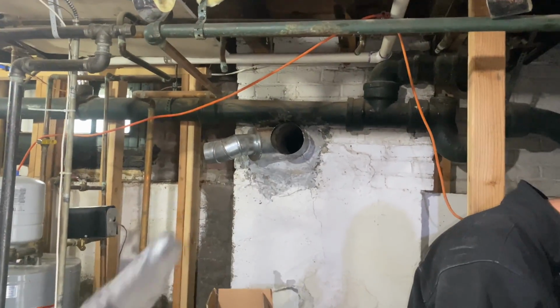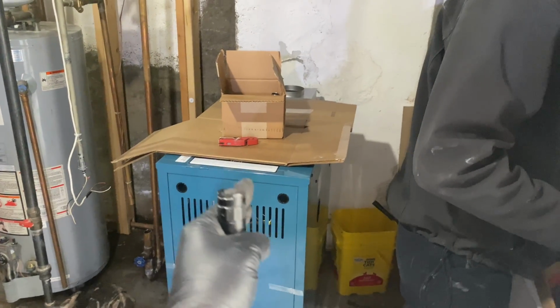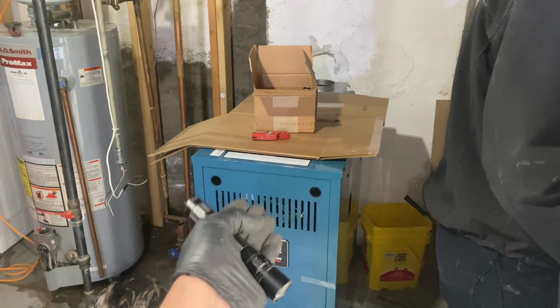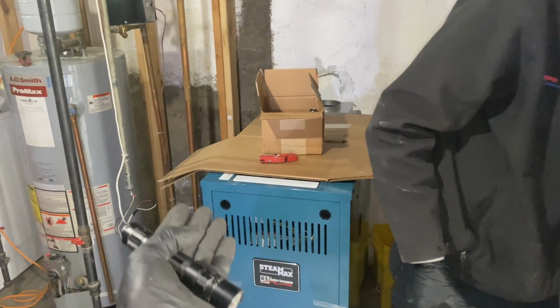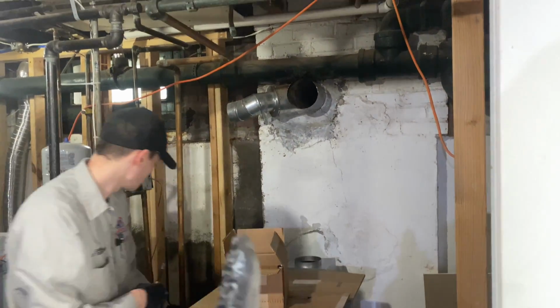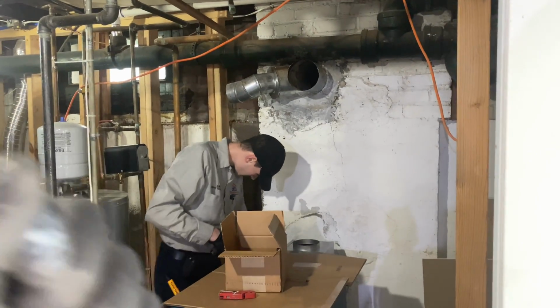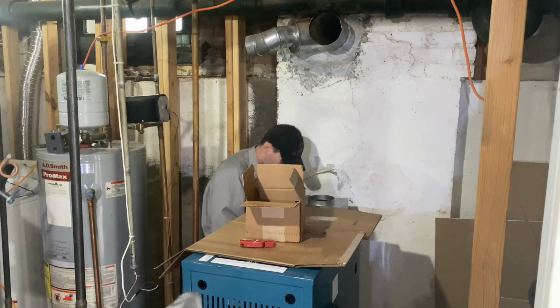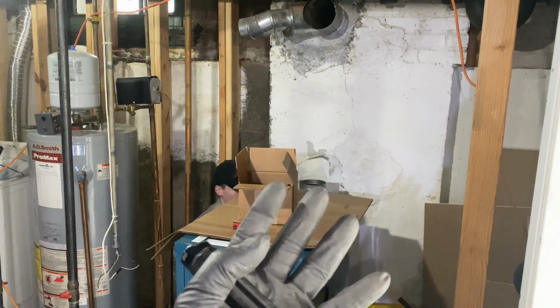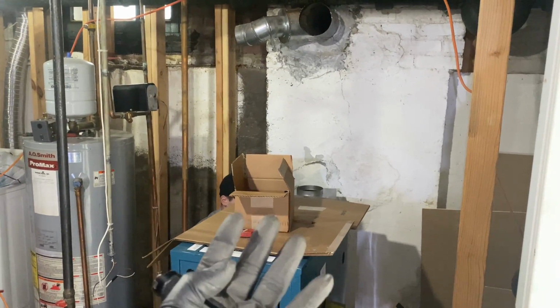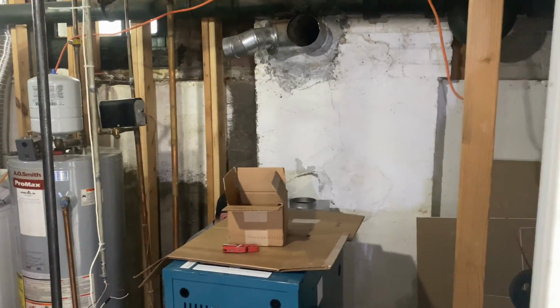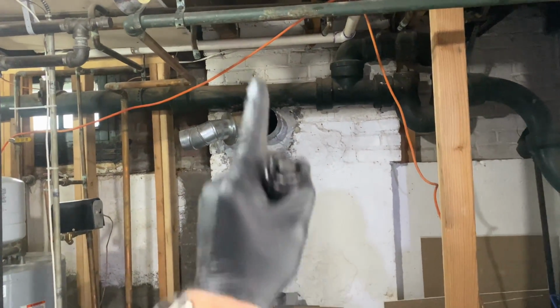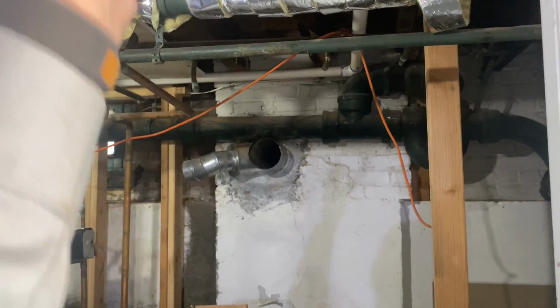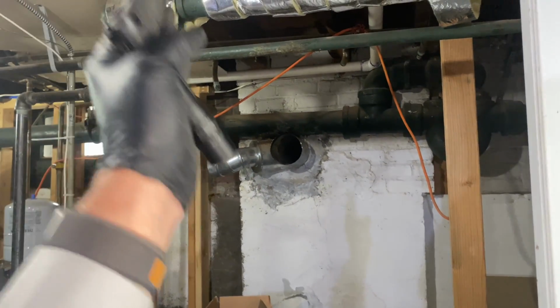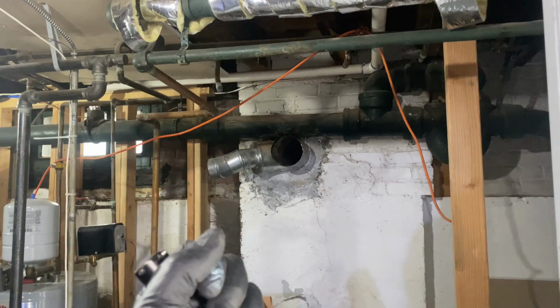The reason is that the temperatures are significantly lower than oil-fired equipment. This boiler, for example, will have a stack temperature between 375 and 420 degrees. The problem with a terracotta lining is that those exhaust gases also contain vaporized, very acidic exhaust gases. As the exhaust gases cool, the vapor inside them will start to condense, and then that very acidic condensate, right?